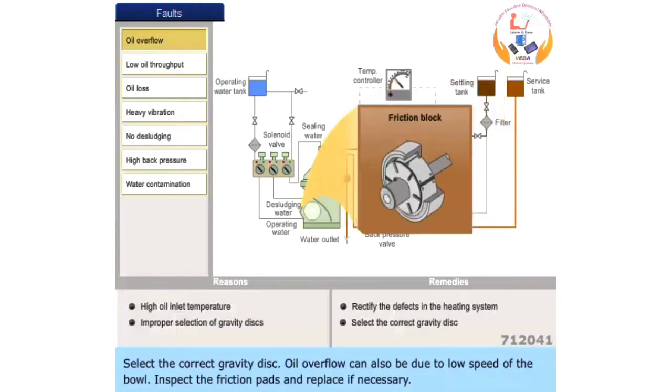Oil overflow can also be due to low speed of the bowl. Inspect the friction pads and replace if necessary.